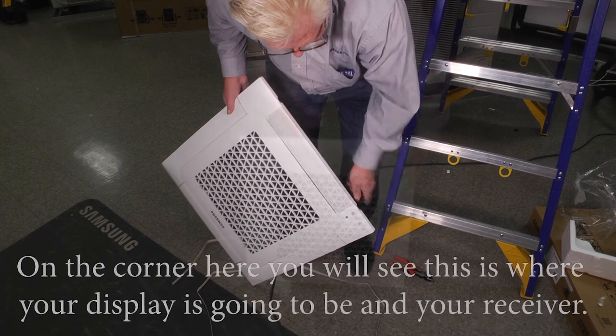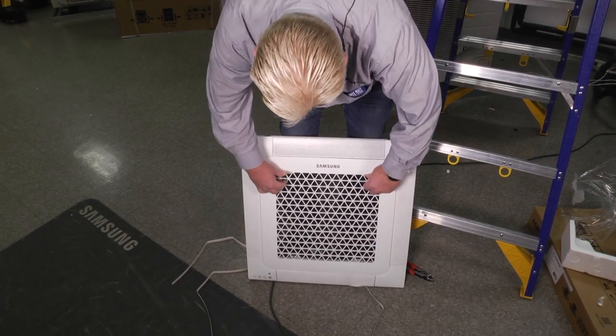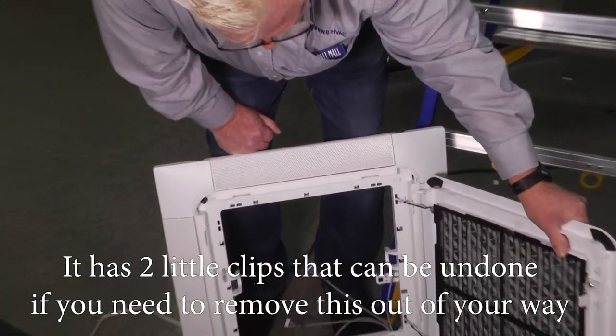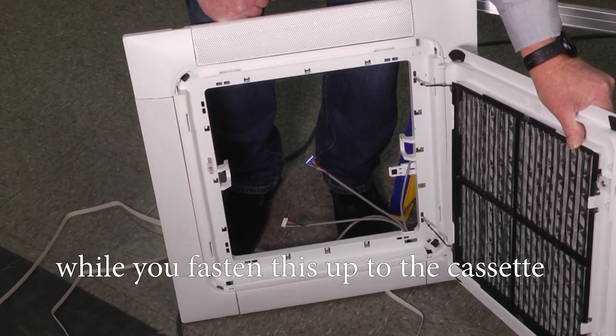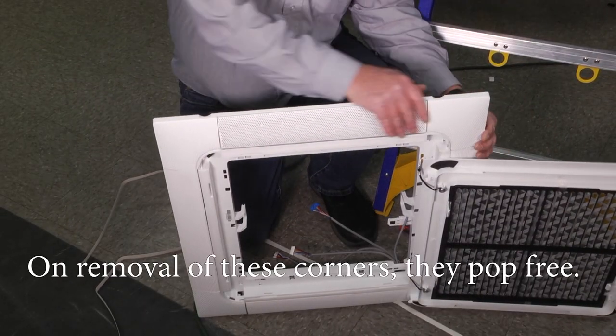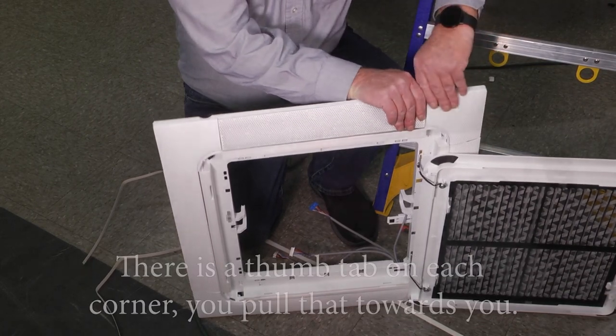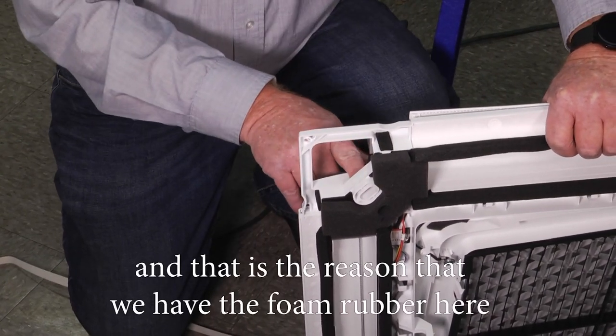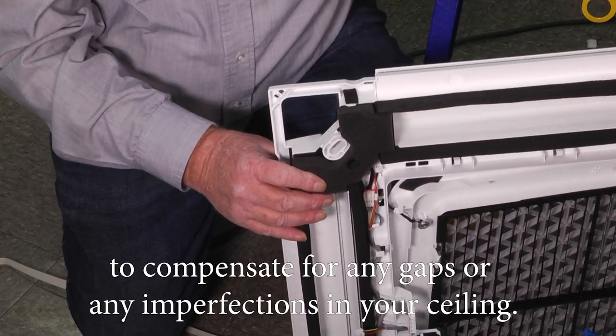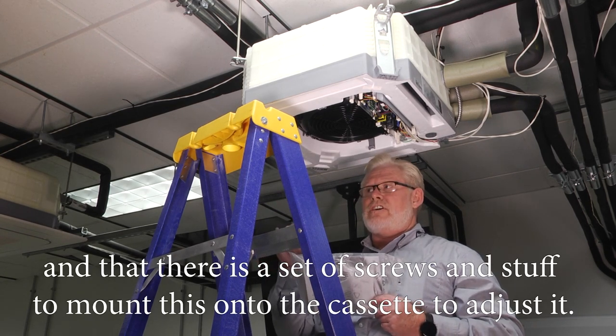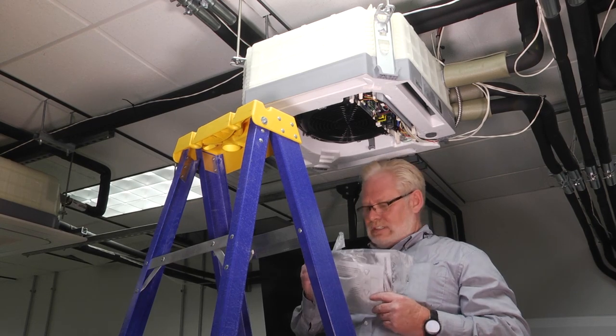Once we get it all unpackaged, you're going to want to remove the cover on the corners. Here you'll see this is where your display is going to be and your receiver. On the filter removal, you're going to pull the two clips down, this comes open. It's got two little clips that can be undone if you need to remove this out of your way while you fasten this up to the cassette and while you gain access to your control box to put your harnesses in. On removal of these corners, they pop free. There's a thumb tab on each corner you pull that towards you, the corners come loose. We have to do that on all four corners so that we can adjust this to our ceiling, and that's the reason why we have the foam rubber here to compensate for any gaps or any imperfections in your ceiling.